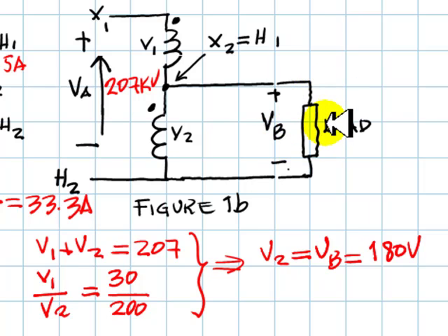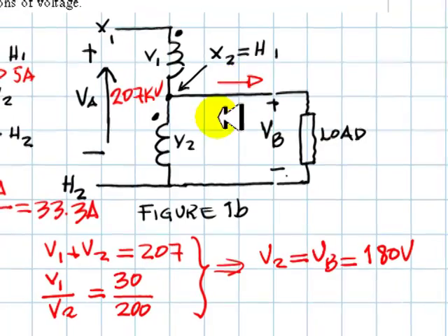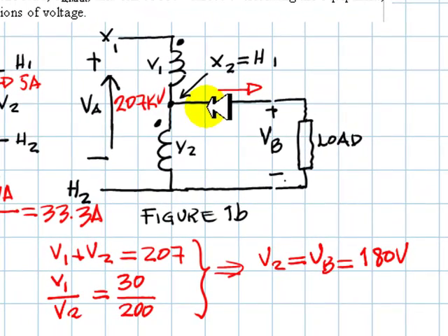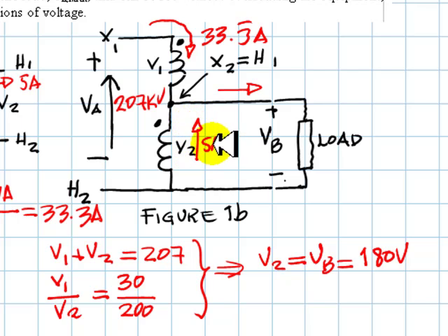The maximum load here implies maximum current here. Well, let's talk about maximum currents. You and I know that the maximum safe current we can feed into this coil is how much? 33.3 amps. That is correct. But when we do that, out of this dot, we will have 5 amps pumping out, like so, 5 amps. That is the maximum current condition in this transformer.